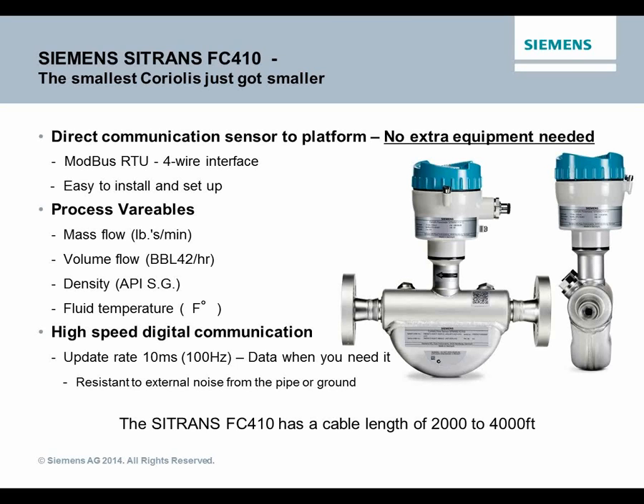So as I was saying, this is one of the newer small meters, a half-inch tube sensor. It weighs about 10 pounds and is about 10 inches long, so it's an extremely small meter. This particular device also has a digital interface, so as the information comes off the tube, it goes directly into an analog to digital converter, and then everything from that point on is communicated via Modbus. So there is no display, there are no push buttons. You interface with this with either a 4-wire terminal block or a quarter-turn 4-wire Class 1 Div 1 terminus, and it makes for a very quick and very easy interface. And if you're using Modbus, it's pretty much a one-click go.